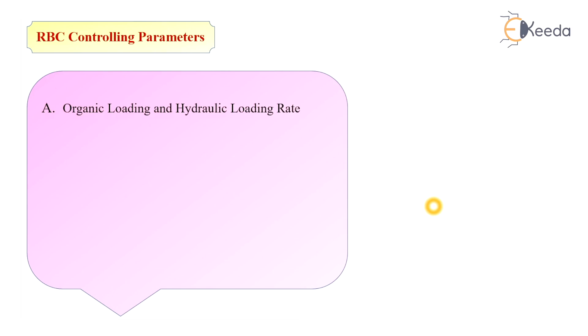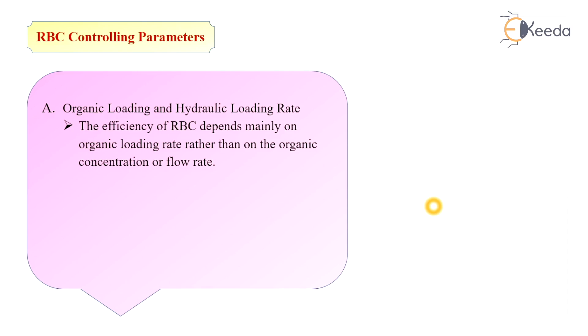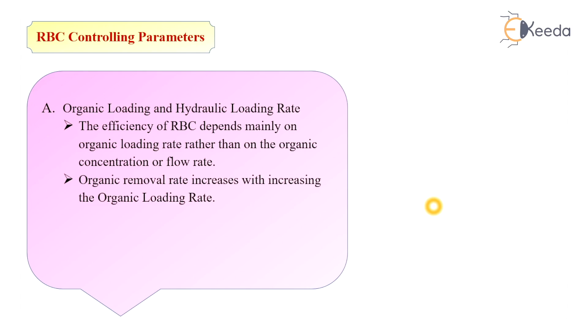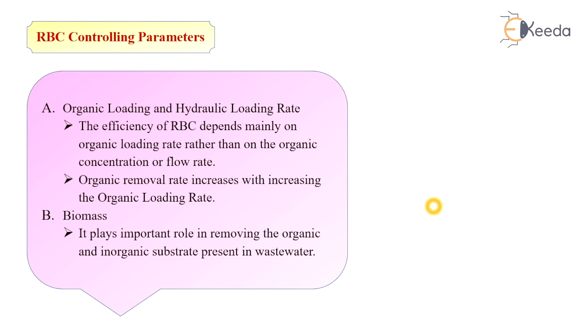There are a number of controlling parameters in RBCs. The first important parameter is organic loading and hydraulic loading rate. The efficiency of RBCs depends mainly on the BOD loading rate rather than the organic concentration or flow rate alone. Organic removal rate increases with increasing organic loading rate. Biomass plays an important role in removing organic matter and inorganic substances present in wastewater.